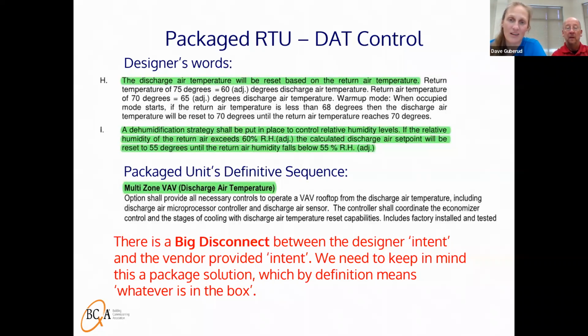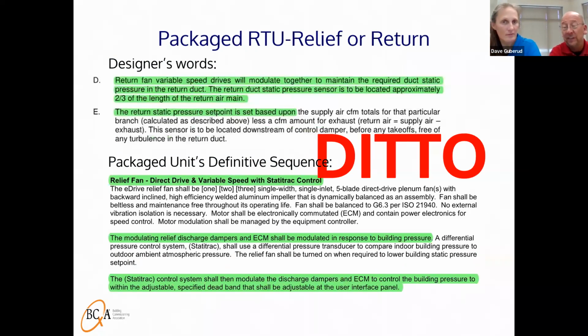And so having them both in the same room and indicating how this is really going to work matters. Just to take one little jaunt off of this, you can get a sequence of operation book from the rooftop manufacturer, and they might have 4 different ways spelled out, like morning warm up, discharge air control or static pressure control. But we don't want the final record submittal to have all 4 of those in there. We just want to say which one you are using for this project and bring that into the document. The same held true here. The designer's sequence of operations spoke to return fans and return fan static pressure, yet it's a relief fan. So the engineer actually made a little mistake here, and again, we have to make sure that the unit is going to operate as intended.